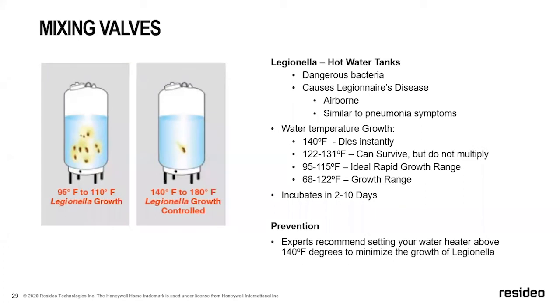However, if we set our water heaters to 140 degrees, that would scald someone, right? So we can set it that high, but we need a mixing valve to mix it back down to where it delivers maybe 110, 115, maybe 120, depending on what you set it to, what your customer wants out to the facility. So for prevention, experts recommend setting your water heater above 140 degrees to minimize growth of Legionella. So one thing the mixing valve allows you to do is set your water heater's AQUASTAT higher than normal and still provide protection to the home.